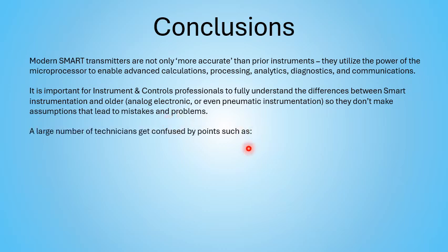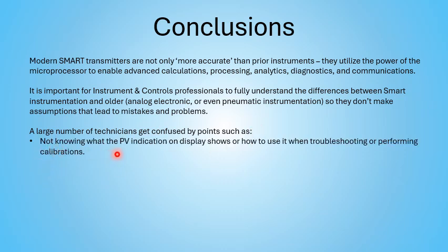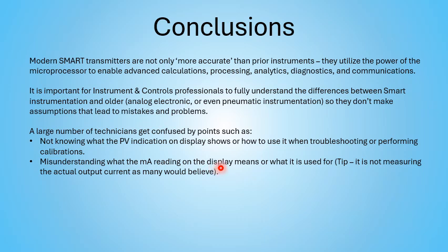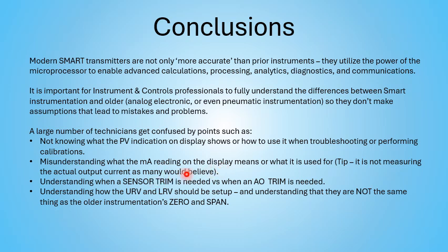A lot of technicians and engineers get confused by certain points on smart transmitters, such as not knowing what the PV indication on the display shows or means, or how to use it when they're troubleshooting or performing calibrations. They misunderstand what the milliamp indication on the display means or what it's used for. And tip, as I said earlier, it's not the actual output current, as a lot of people seem to believe. Understanding when a sensor trim is needed versus when an analog output trim is needed. Understanding how the upper range value and lower range value should be set up, and understanding that they are not the same thing as the older zero and span.